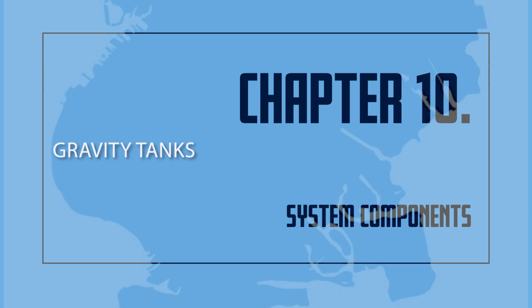The gravity tank must always have a full supply of water. A full tank of water is needed to ensure the sprinkler system works properly during a fire. Keeping the tank full of water also prevents wooden tanks from shrinking. A full tank of water helps keep steel tanks from rusting.